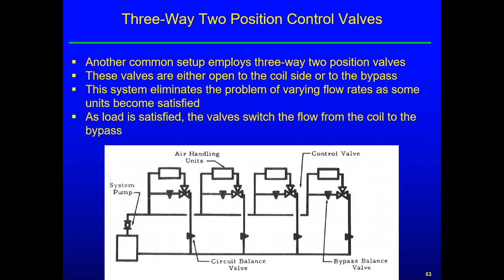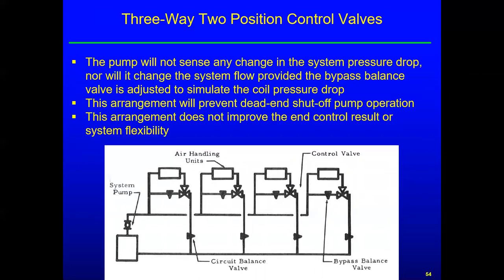So that's about it. It's probably under thermostat control. When the space is satisfied, bingo, you switch to the bypass, and the pump never knows the difference here, because you set up the bypass to have the same pressure drop as the coil. And so back and forth, the pump doesn't know where the water's going. Okay, so more on that.